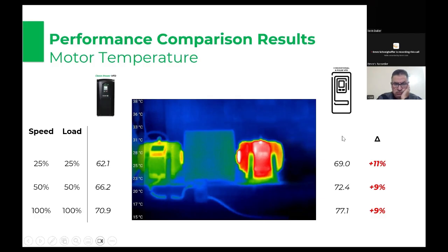And on that note, also asking, we use VFDs in refrigeration and HVAC compressors, which are cooled by the refrigerant, so the 10% less is not adding load to the refrigerant. Okay, let me understand that. Sorry, can you repeat that question? Emery, can you take the mic? Yeah, there's 10% less heat generated by the motor, because most motors are encased in refrigerant when it's coming back from the evaporator. So that's not adding heat to the refrigerant.